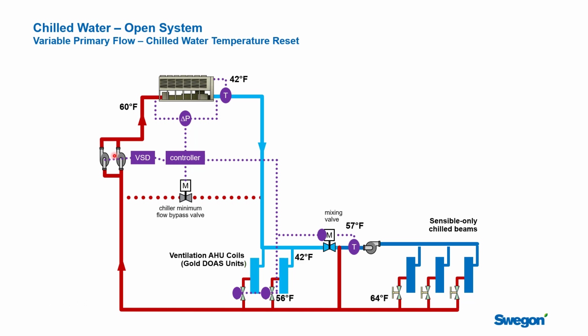Let's talk a little bit about chilled water reset. It's a well-known energy savings methodology in a building that if the conditions are right, the cooling loads are lower, and the dry bulb or the dehumidification requirements allow, you could actually try resetting the chilled water temperature up from the design conditions. And that's particularly attractive because as the weather moves into the fall or early spring, you've got a chiller plant that's making 42-degree water. The beams only need 57-degree water. A chilled beam system would appear to be a system that would benefit greatly from being able to raise the chilled water temperature during lighter loads for the energy savings. As you raise the chilled water temperature off of the chiller plant, you'll get a significant improvement in the COP of the chiller plant. So it is something to consider.